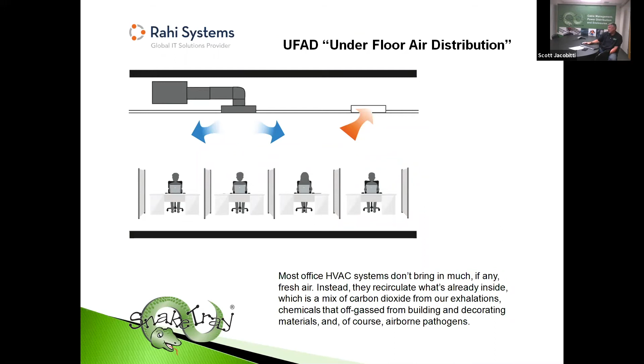So when we use a raised floor, the dynamics change. The inflow comes up from the raised floor space—that's the delivery system. Each person in the space has their own individual air diffuser, letting them control the temperature and how much air comes into their space. As you can see from the graphic, that air doesn't mix with the outflow until well after the user area, so we have these little air columns coming up at each individual workstation.